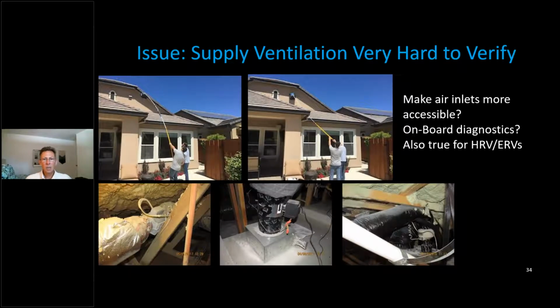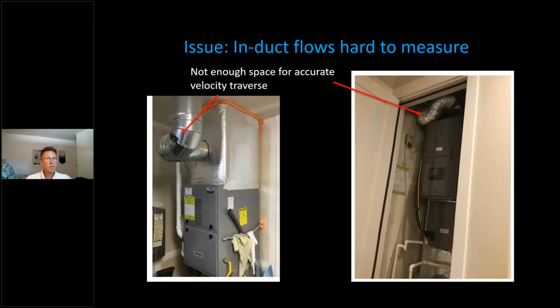Now I want to mention a couple of issues the standards aren't currently doing a very good job with, partly due to practical issues. Supply ventilation is really hard to verify. Even though the standard says to measure the flow rate of the ventilation device, it's really hard to actually do in the field. This is an issue we've got to address if we expect supply ventilation systems to deliver the proper amounts of ventilation air. In-duct flows are also hard to measure, so that's another challenge we have to deal with.